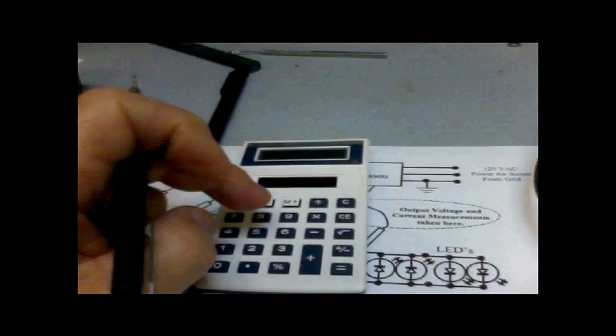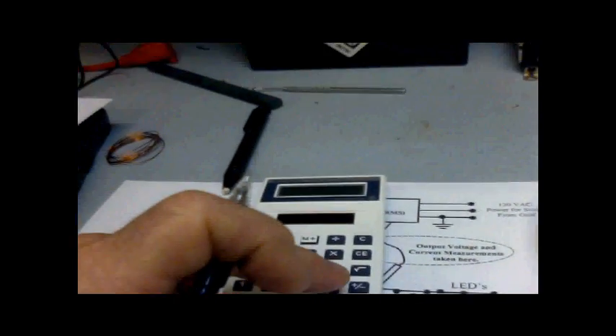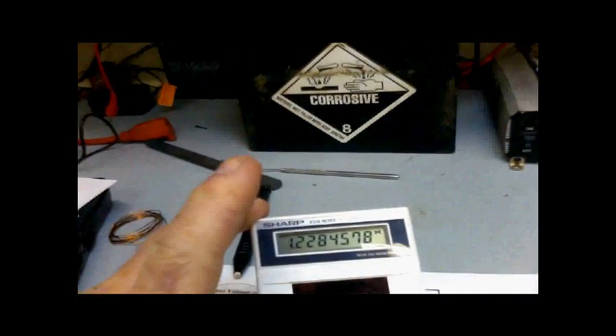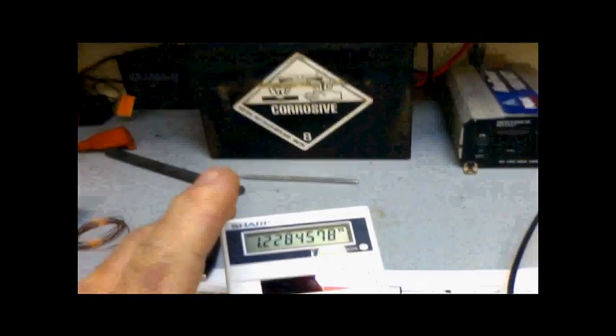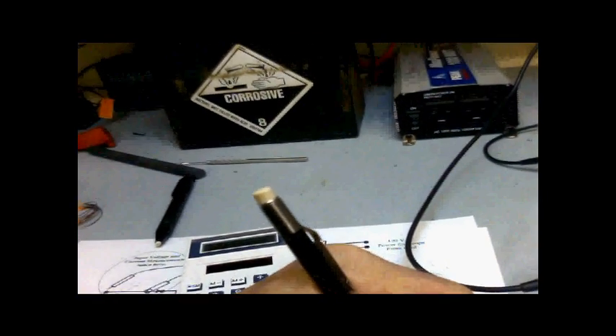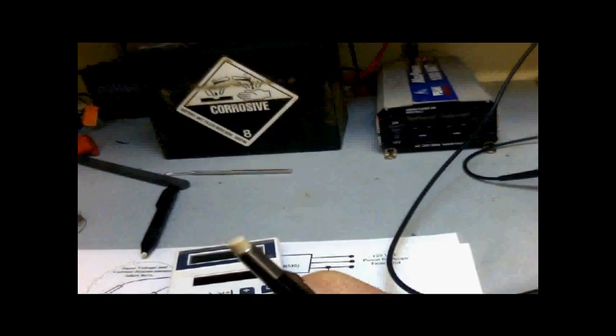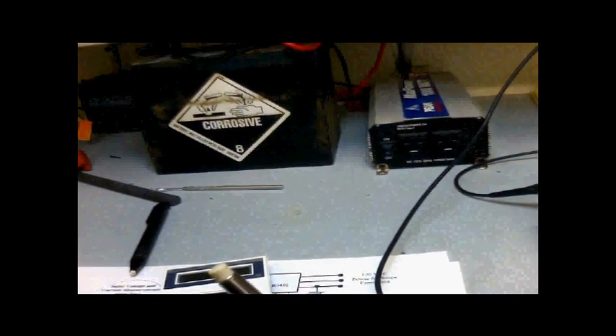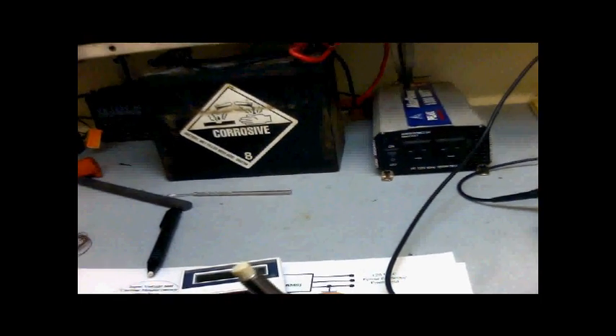Which equals 629. And my COP would be my output of 772.7 divided by my input power, which is 629. So let's do that: 772.7 divided by 629 equals a COP of 1.228, we'll call it 1.23, rounding up.